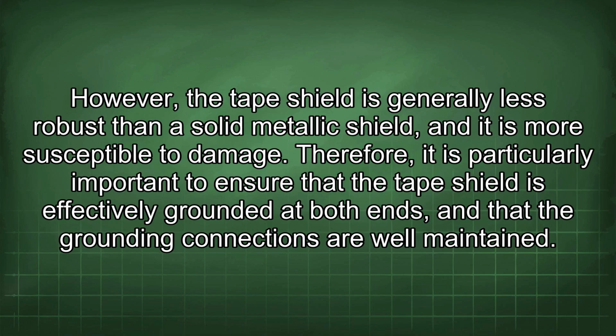However, the tape shield is generally less robust than a solid metallic shield, and it is more susceptible to damage. Therefore, it is particularly important to ensure that the tape shield is effectively grounded at both ends, and that the grounding connections are well maintained.